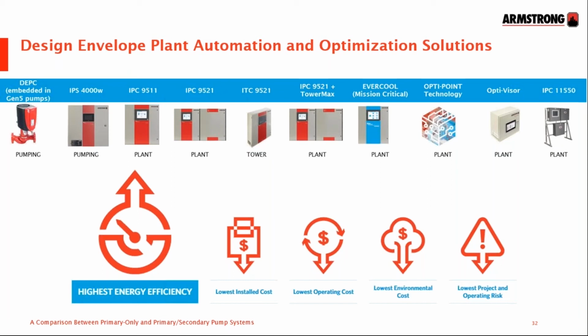We do the TowerMax upgrade from the IPC 9521, which will then operate the cooling tower fans and pumps in an optimized way to minimize the power absorbed by the chiller and maximize the amount of cooling that the towers can provide. Evercool is our mission-critical controller for a data center chiller plant. Opti-Visor and IPC 11550 are our patented algorithm chilled water optimization plant, and OptiPoint is going to be our next release, a chiller optimization plant that uses machine learning to develop the lowest energy costs for a particular chiller system. That's summarizing it.